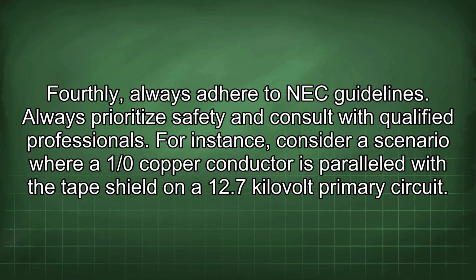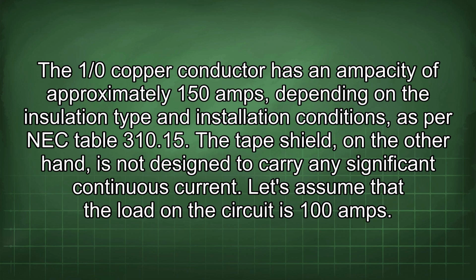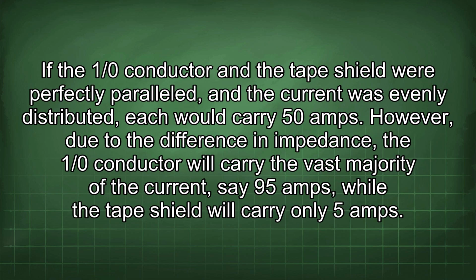For instance, consider a scenario where a 1/0 copper conductor is paralleled with the tape shield on a 12.7 kilovolt primary circuit. The 1/0 copper conductor has an ampacity of approximately 150 amps, depending on the insulation type and installation conditions, as per NEC Table 310.15. The tape shield, on the other hand, is not designed to carry any significant continuous current. Let's assume that the load in the circuit is 100 amps. If the 1/0 conductor and the tape shield were perfectly paralleled and the current was evenly distributed, each would carry 50 amps. However, due to the difference in impedance, the 1/0 conductor will carry the vast majority of the current, say 95 amps, while the tape shield will carry only 5 amps.